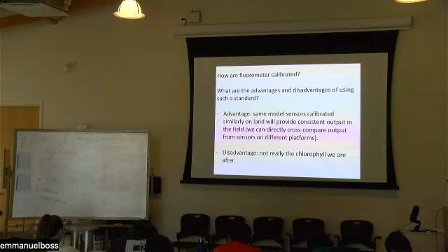And so you make up your own standards, you run them in your own spectrophotometer, you check the dilutions in your spectrophotometer, and then you use that to calibrate your HPLC and your turner. So every instrument that you're using is a step away from absorption.